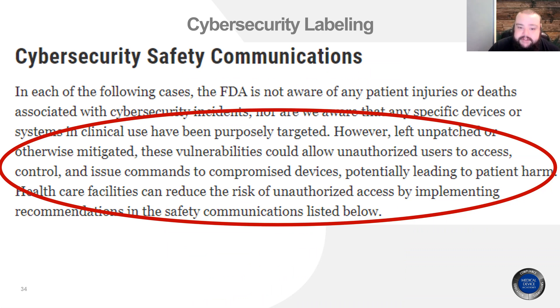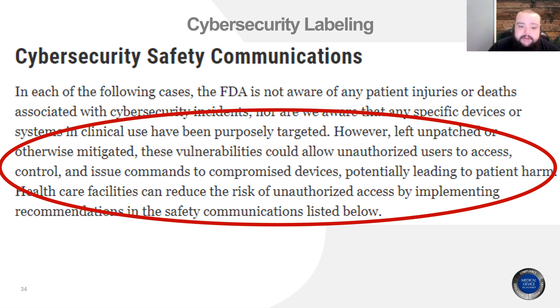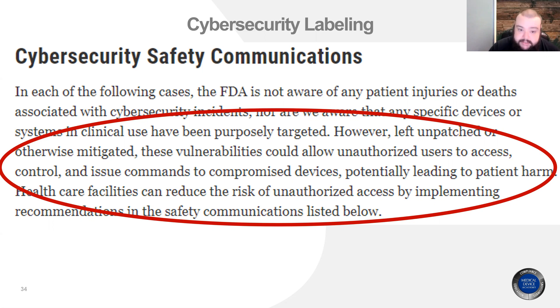These cybersecurity communications are vulnerabilities that the FDA has acknowledged in cases where they don't know of patient injury or death, but if unmitigated, could lead to patient harm or compromise of protected information. So if you're in the process of your 510K submission, look at what's happening to the predicate devices around yours to see what applies.